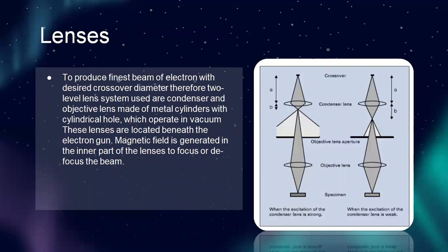Next, I will explain lenses. To produce the finest beam of electrons with the desired crossover diameter, a two-level lens system is used consisting of condenser and objective lenses made of metal cylinders with a cylindrical hole, which operate in vacuum. These lenses are located beneath the electron gun, a magnetic field is generated in the inner part of the lenses to focus or defocus the beam. The diagram shows strong versus weak excitation of the condenser lens, specimen, objective lens, objective lens aperture, condenser lens, and crossover.